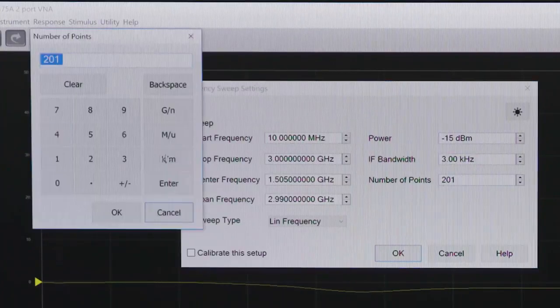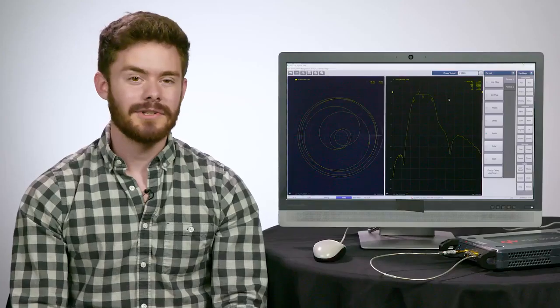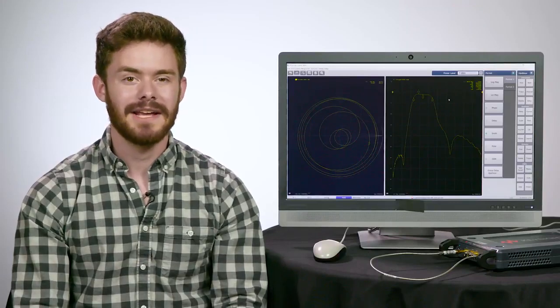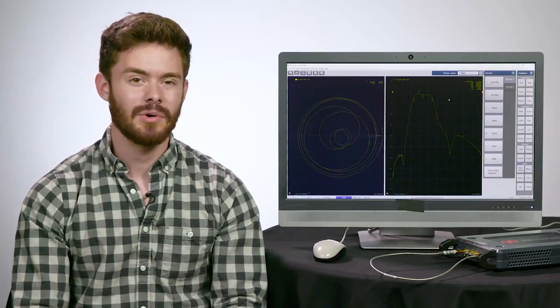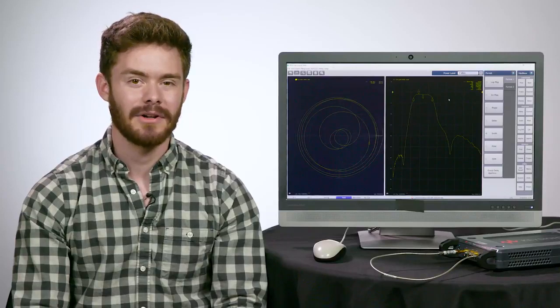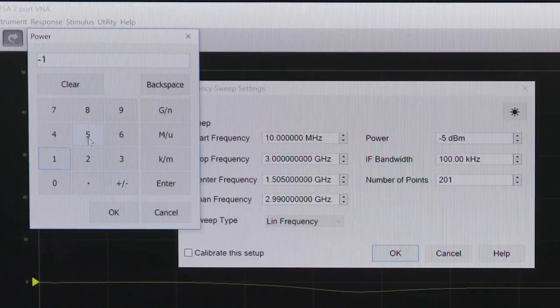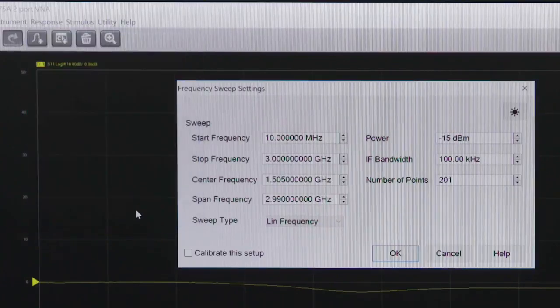It's important to remember here that this new USB VNA's source power must be set correctly in order to avoid damage or compression inside the E-cal module. The power for this should be set to minus 15 dBm for the calibration operation. Now that we're done with that quick setup, let's get calibrating!